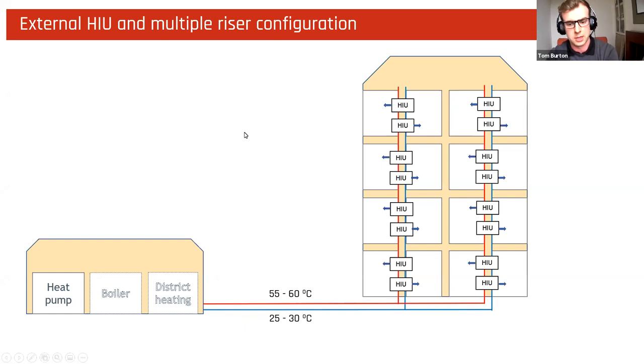And this would look something a bit like this. Whereas before we had one riser going up with horizontal pipework on each floor, you've now got basically vertical pipework only. These risers run up with two HIUs per floor, per riser, which means it's not one riser per flat, it's one riser per two flats where this is possible. Having an odd number of flats on a floor slightly complicates things, but in the grand scheme of things it doesn't swing things out of favor of these.